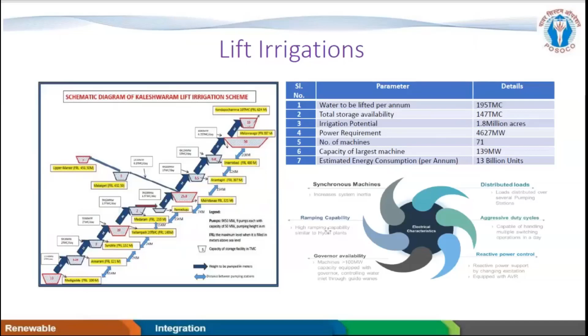It's like a lower reservoir somewhere and a higher one on the higher side. These span around 150 to 300 kilometers. In between, whatever the tank size we are seeing, everywhere pumps of different capacities are there. Basically, these are all synchronous machines. The highest capacity is 139 megawatt. So if you see, the power requirement in this project is 4,600 megawatt, split into small capacities. These are synchronous machines. They can give me inertia. They have distributed loads. I can fast start and stop. Reactive power, because being a synchronous machine, it can give me reactive support. It can give me governor response. It can give me ramping capability. This is very unique. Of course, presently it is just to show a sample example.